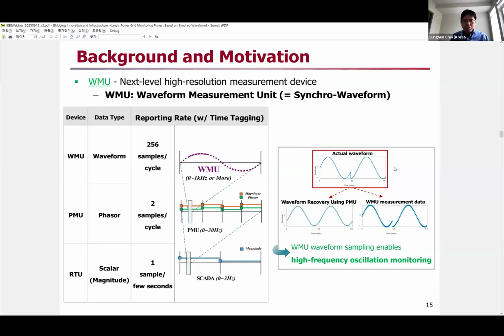Why is it important to use a WMU? Here you can see the actual waveform, with some glitches. With a PMU, this waveform is changed to phasor data, which is sent to the upper layer monitoring system, and this phasor can be used to reconstruct the waveform. But the PMU cannot see these glitches, while the WMU can see this kind of glitch or high harmonic features. So high frequency oscillation monitoring is required with this kind of WMU device.